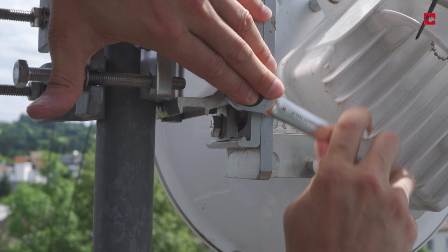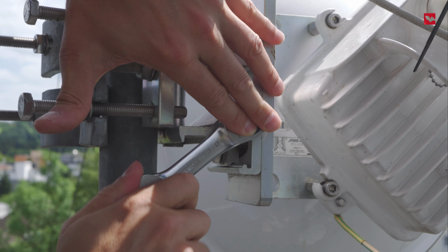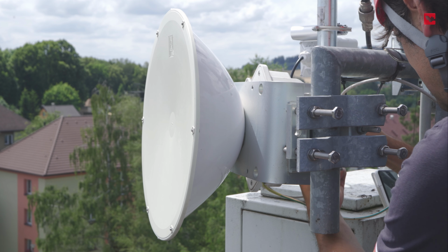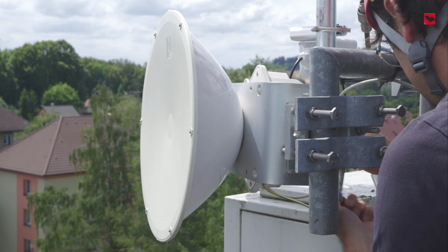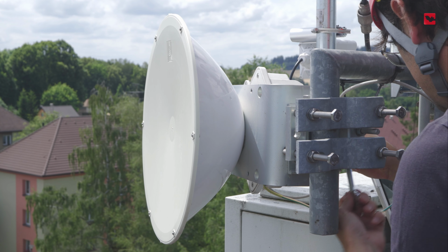Now he switches to the vertical screw, starting down, because going up the antenna works as a counterweight. Scenarios are similar to horizontal alignment, but since we should be getting close, he's also looking at the RSS value, comparing it to the calculation.